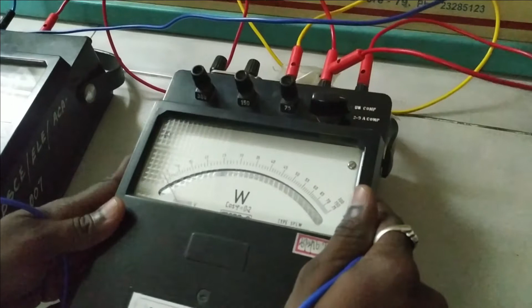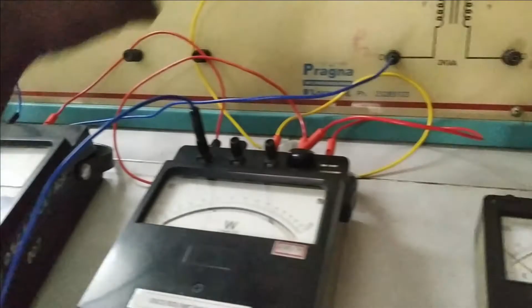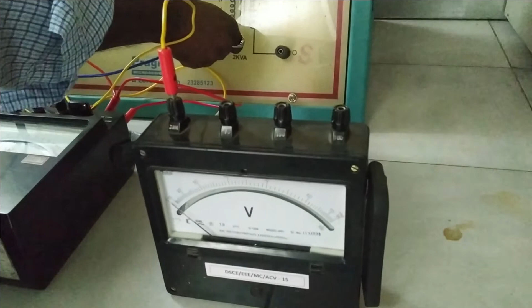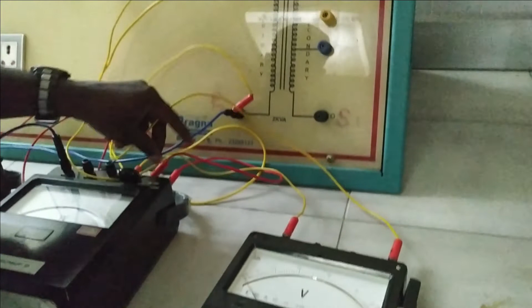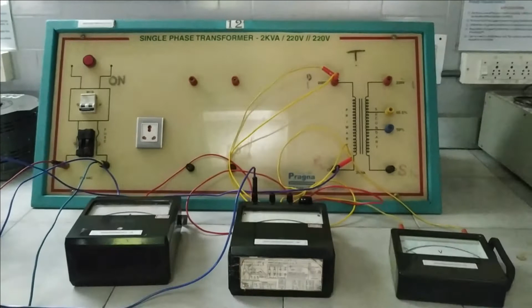Next, the wattmeter V: the selected voltage range for open circuit test is 300, and it should be shorted to P2, the neutral terminal of the auto transformer. Then across P1 and P2, the voltage to be applied is measured. For that we are using a voltmeter with a range of 0 to 300 volt, connected across P1 and P2. So this is how exactly the open circuit test and short circuit test connection goes, and this will be performed on a single phase transformer of rating 2 kVA, 220 volt per 220 volt. Next, we will see how exactly the experiment is conducted.